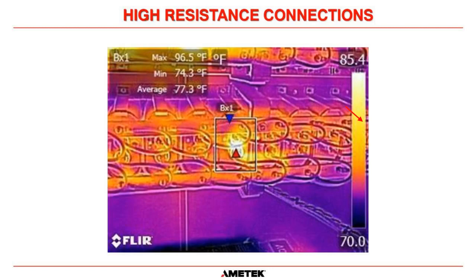Now, this actually was a system that had been in service for a couple of years, and we went out to perform a PM once we had initiated the FLIR cameras into our service operations. And this problem had not been caught the year before because we hadn't been checking for thermal imaging. And in this circumstance, you can see in the middle there that this red triangle is pointing at the hottest part of this machine. That is not supposed to be that hot. You can see here basically what the temperature should be for a normal capacitor. And as you can see, the maximum temperature there is 96.5 degrees Fahrenheit, which is 20 degrees above the average, approximately.